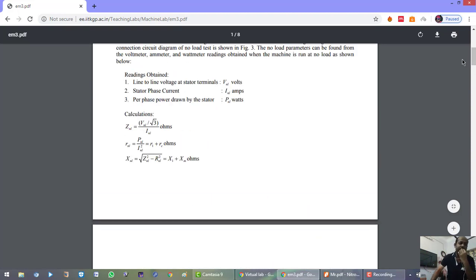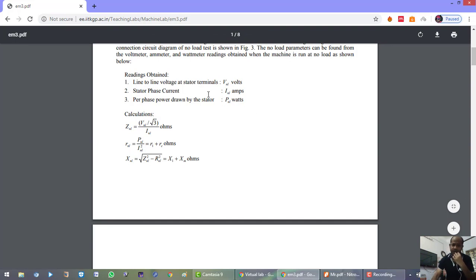As covered in lectures already uploaded on my YouTube channel, in the no-load test and block rotor test of a three-phase induction motor, we calculate the line-to-line voltage and the phase current for a star-connected induction motor. We measure power by the two-wattmeter method, from which we can calculate the impedance of the circuit, since for a star connection the phase voltage equals line voltage divided by root 3, divided by current.